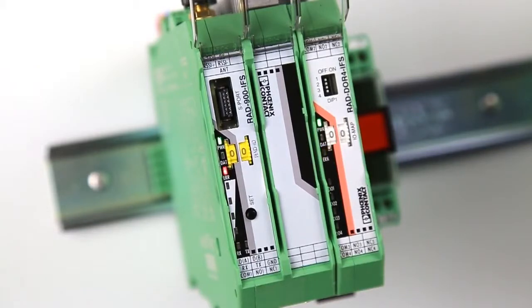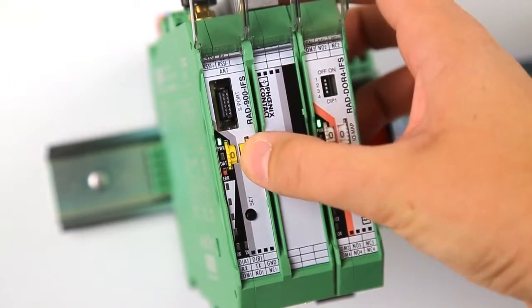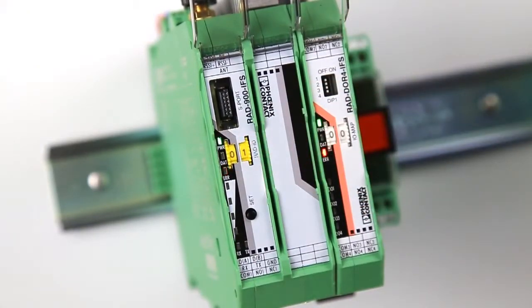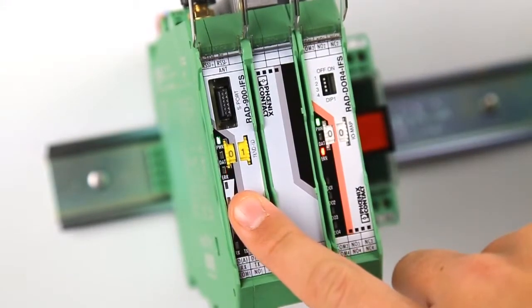First, configure one unit to master by setting the yellow thumb wheel to 01. To read in the thumb wheel setting, push the set button for one second.